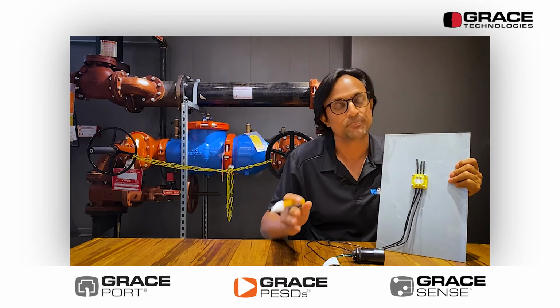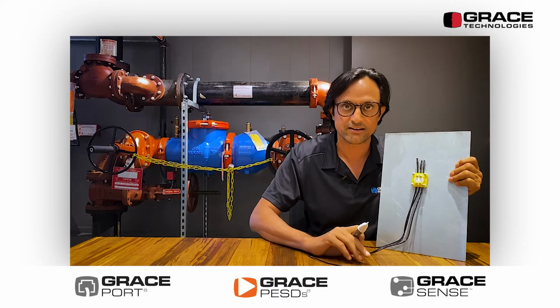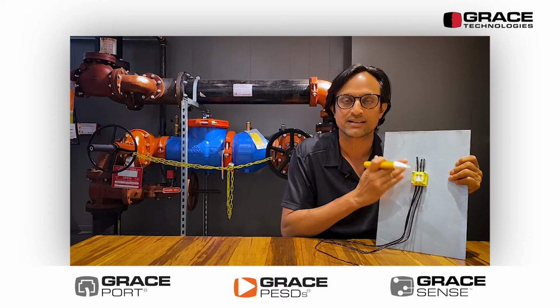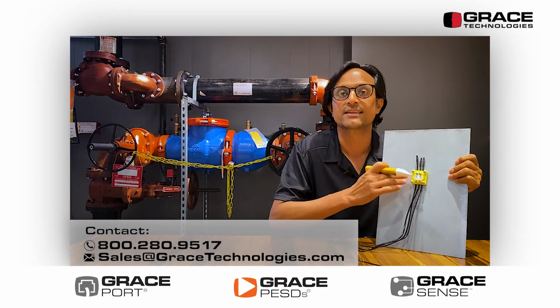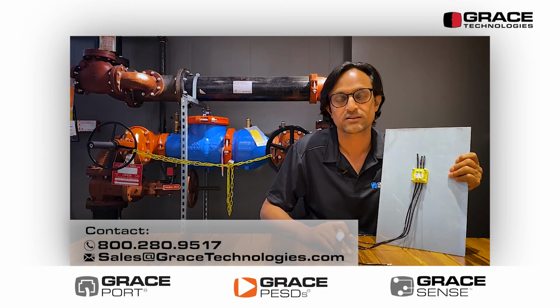That's the one scenario. And the second scenario is basically you don't have the voltage indicator and you want to use just this R-3K product alone on a standalone basis. In that case, you would run a separate set of wires as what I'm showing here, and then you'll hook it up to your line or load side of your source to measure the voltage presence.